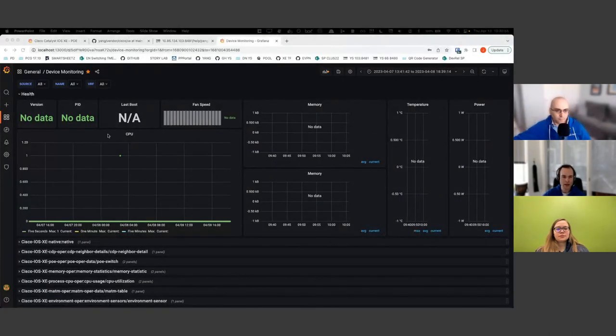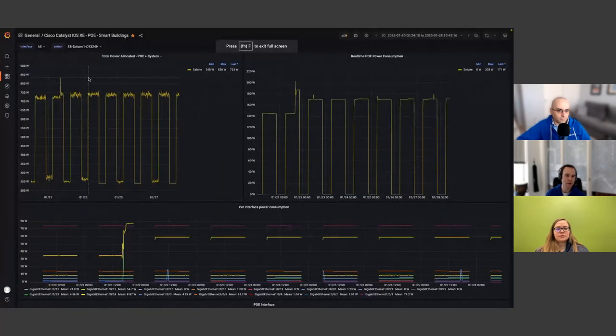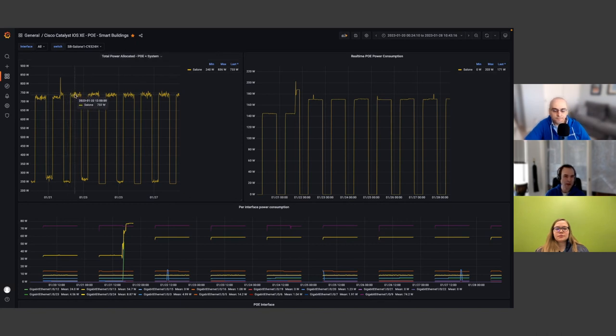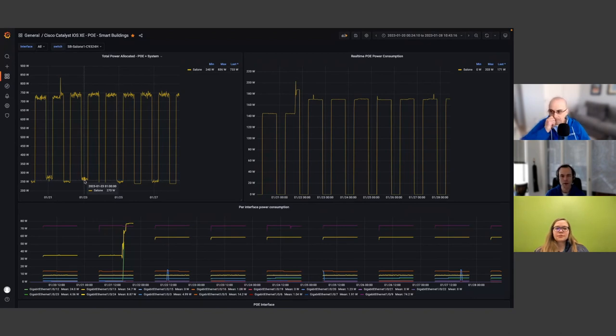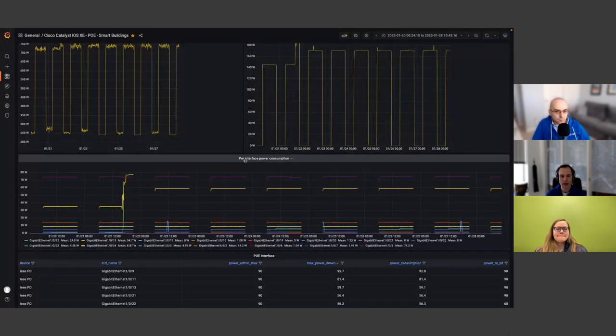Let's look at a better dashboard that has more data. This is the PoE for smart buildings dashboard. On the top left we have the total PoE and system power allocated. In the daytime we're seeing about 700 watts of utilization, and in the evenings when devices are disabled or less used in the smart building, power draw reduces to around 250–270 watts. The way we're able to get the savings is at a per-port level — looking at individual ports and understanding how much power each is drawing from PoE.